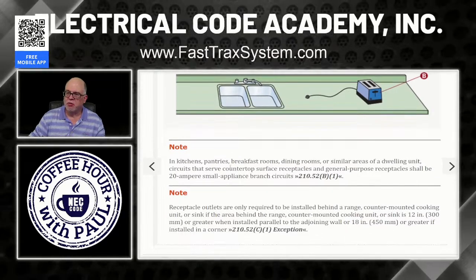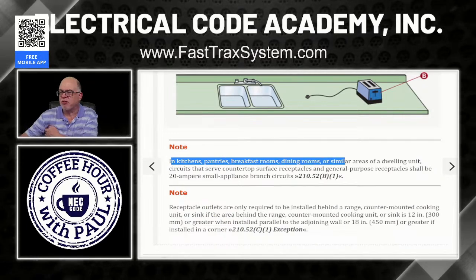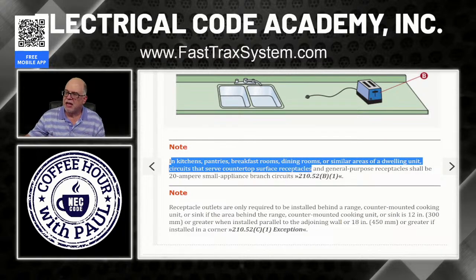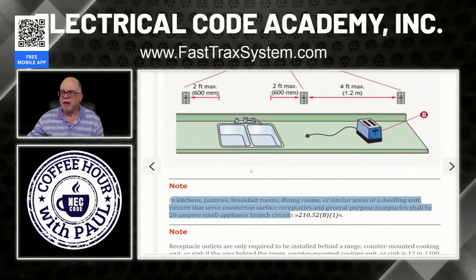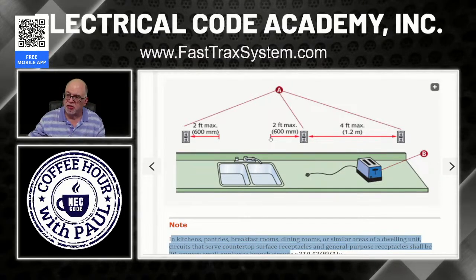Now let's look at some notes here. It says, in kitchens, pantries, breakfast rooms, dining rooms, and similar areas of a dwelling unit, circuits that serve the countertop surface receptacles and general purpose receptacles shall be 20 ampere small appliance branch circuits. So that is 210.52(B)(1). All right, let me make sure everybody's clear. The same small appliance branch circuit that serves these receptacles on the counter is also going to serve the receptacles around your kitchen, around the room.